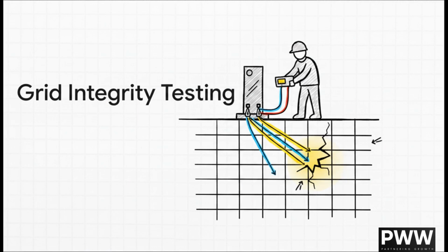To keep those potentials in the safe zone, the copper grid beneath the substation must be perfectly intact. But think about it. The ground grid forms the backbone of the system, and it generally lies about 600 millimeters below the surface. You can't just dig up an entire live substation to check for a rusty wire. That is exactly where ground grid integrity testing comes in. By using advanced, non-intrusive, high-current injections between different risers above ground, we can evaluate the hidden grid below. It identifies dangerous breaks, underground corrosion, or weak connections without picking up a single shovel.